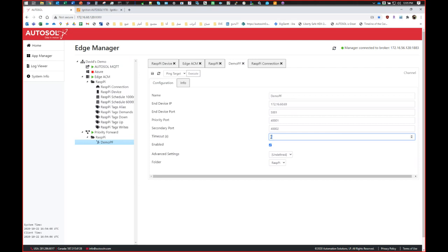So eACM can be polling real-time data to a serial device once a second. EFM collection from Signet can come through, hit priority forward 40,001, that will automatically stop eACM, let that through, and gather the EFM data for as long as it's maintaining connection. Once the connection is released, eACM kicks back up.